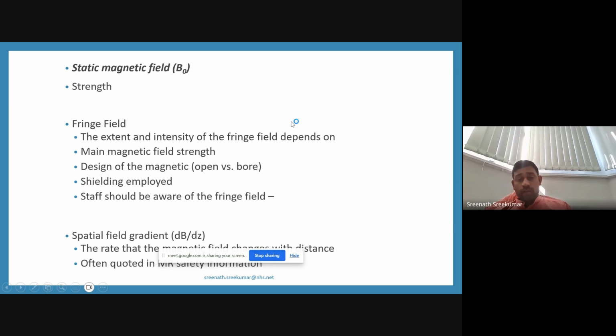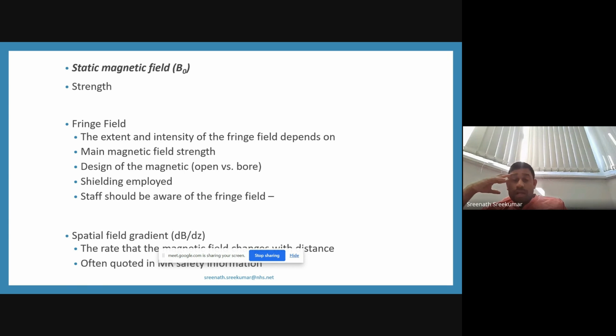And all staff should be aware of fringe field strength and spatial gradient. The spatial gradient and fringe field are different. The spatial gradient is actually the rate of change of the magnetic field with distance. That's the main thing we have to define as a spatial gradient. How much the distance from the machine is reducing the spatial gradient. The further you go from the machine, the more it is reduced, dB by ds. That's the spatial gradient. So if you are going closer to the scanner, there is a higher risk from spatial gradient. If you're going away from the machine, there is a lesser risk.